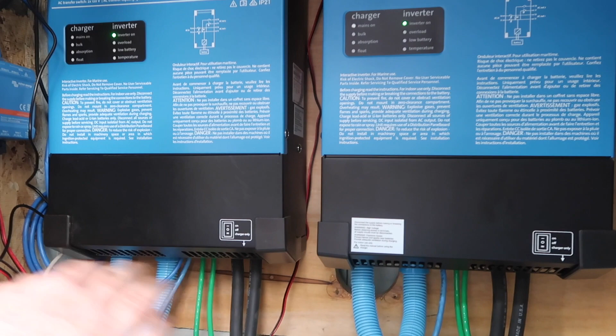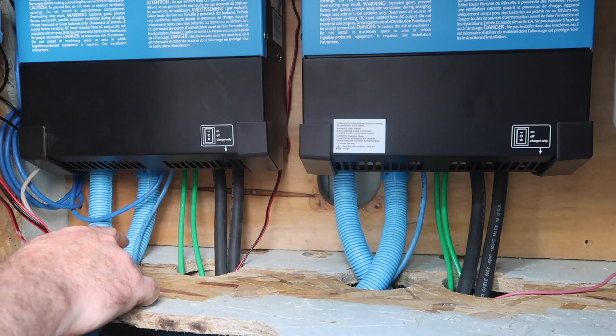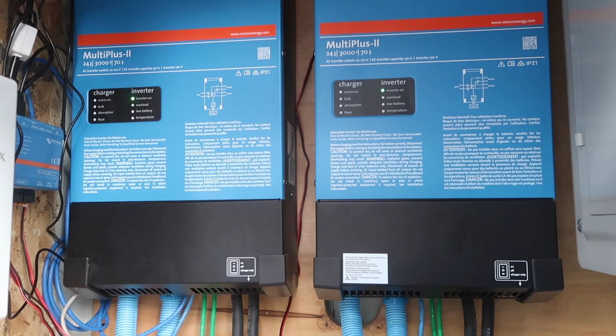They are connected together via a data cable - just a standard Ethernet cable, Cat5 or Cat6, about 3 feet long. This cable shares information between these two units; they talk to each other and are programmed to know each other. So they are coordinated and act as the split phasing for North American 240 volt split phase power. This one's putting out 120 volts and this one is too, and they feed into the second blue conduits that go into the electrical panel. Your electrical panel has a master 50 amp in-feed right here.